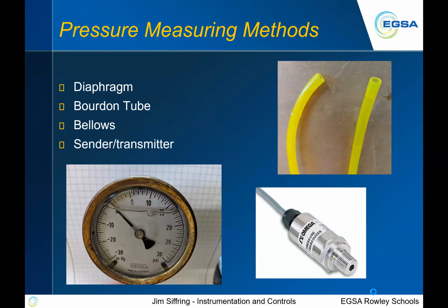If you look at specifications such as inches of water drop, pressure drop across a radiator with a fan, maybe you get 10 inches of water drop, pressure differential. Well, how do you measure that? We'll fill a piece of tubing, maybe 20 feet, up close to full, not full. Want to leave some room at the top of each side.